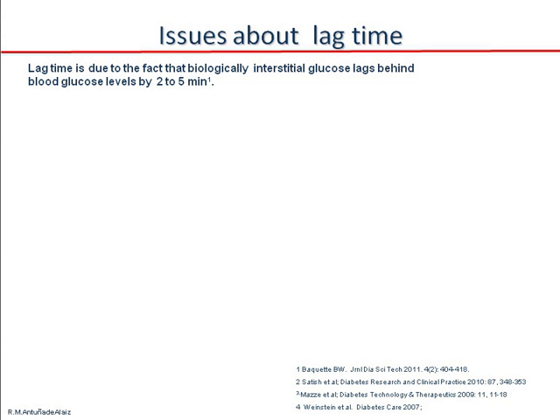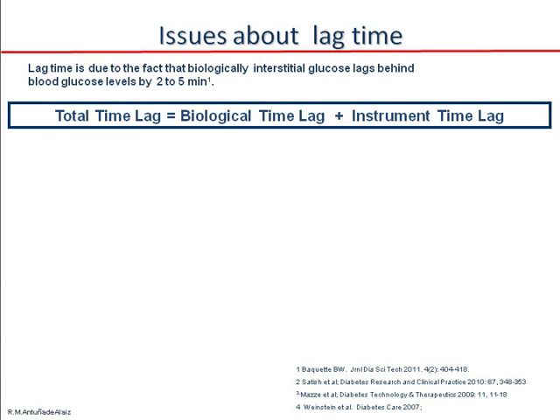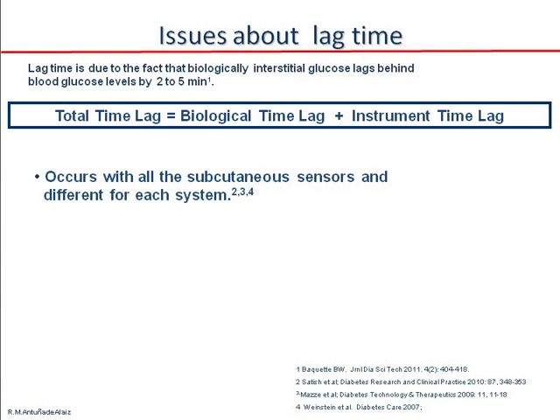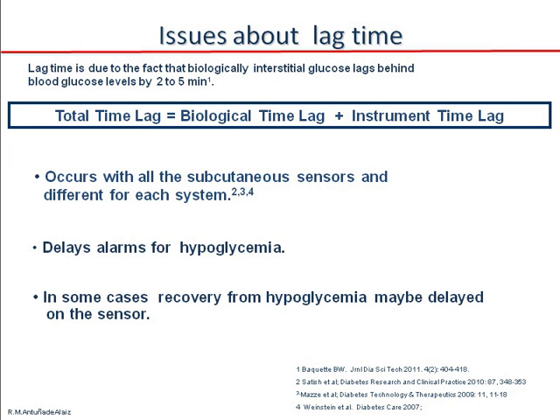There are some important issues about lag time that I want you to understand, and you have to make patients understand it too. First is that lag time is due to the fact that biologically, interstitial glucose lags behind blood glucose levels by 2 to 5 minutes. And the total time lag is obtained by the sum of a biological time lag plus instrument time lag. So it occurs with all the subcutaneous sensors, but it's different for each system. It delays alarms of hypoglycemia. In some cases, recovery from hypoglycemia may be delayed on the sensor and affects calibration of the sensor.